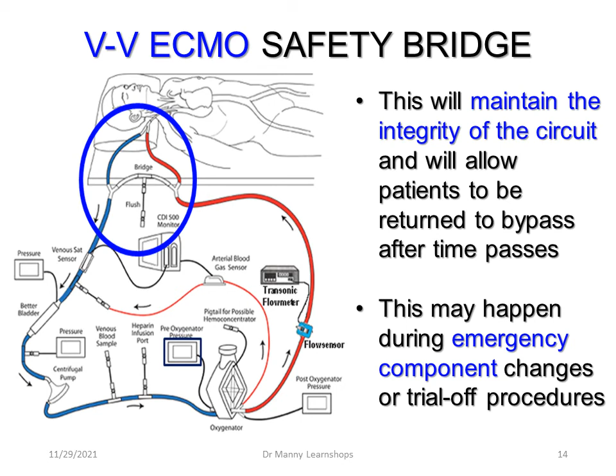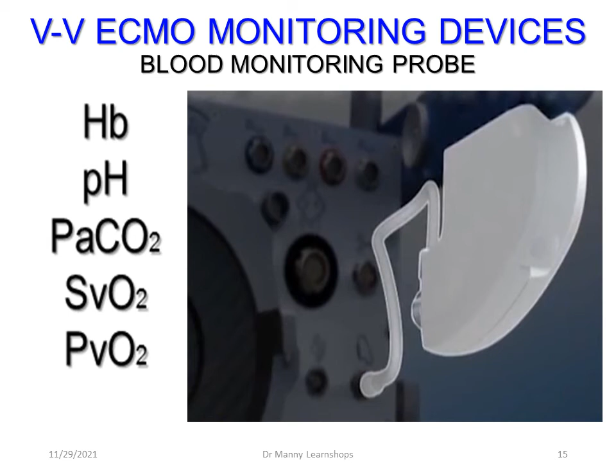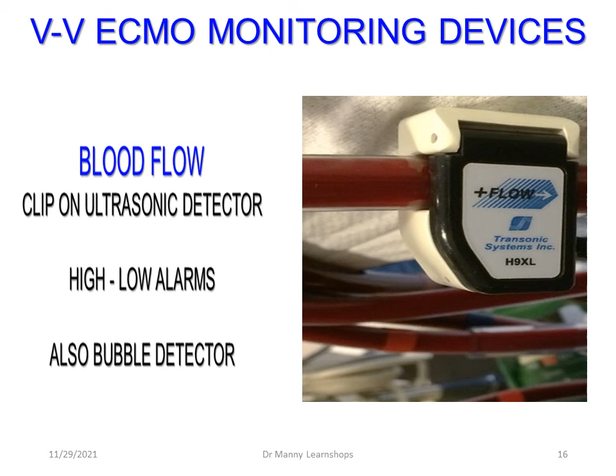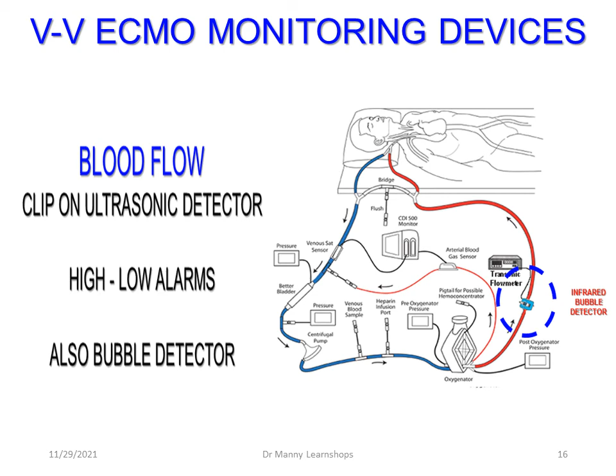There are other aspects related to monitoring devices. In the Marquette system, and I'm sure in other systems as well, you can monitor hemoglobin, pH, PaCO2, PVO2. It also allows blood flow to be monitored with a clip-on ultrasonic detector, which provides high and low alarms, and it also has a bubble detector. Air, to avoid air embolism before the blood goes back to the patient. Located typically in the return line. As I said, this is a clip-on ultrasonic detector which gives you high and low alarms, but also is an air detector, infrared.